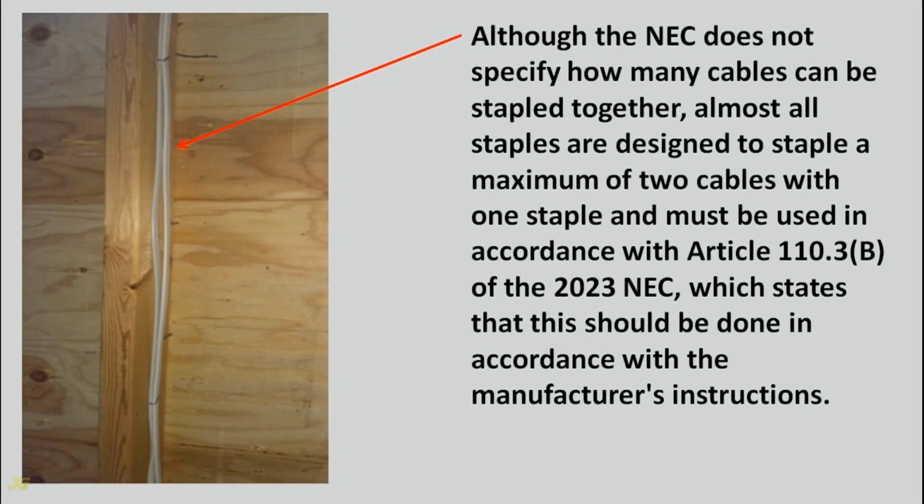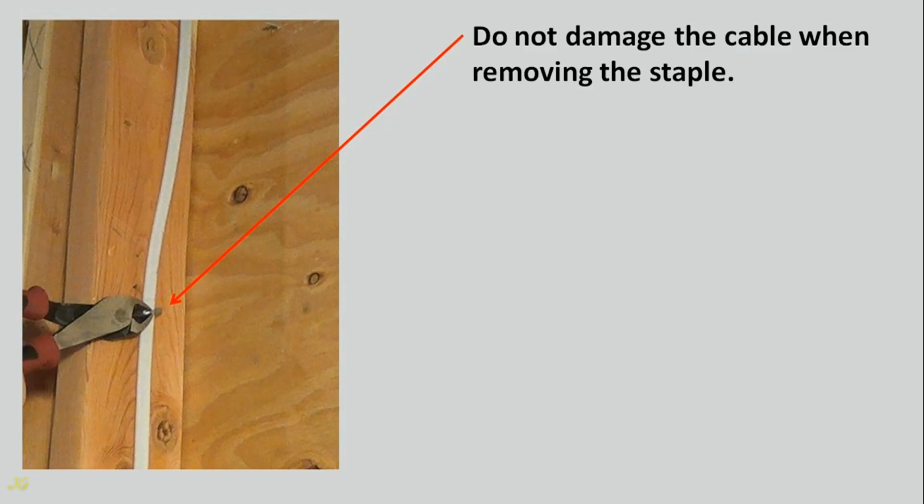Although the NEC does not specify how many cables can be stapled together, almost all staples are designed to staple a maximum of 2 cables with one staple and must be used in accordance with Article 110.3b of the 2023 NEC, which states that this should be done in accordance with the manufacturer's instructions. Do not damage the cable when removing the staple.